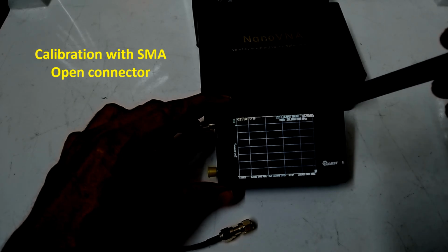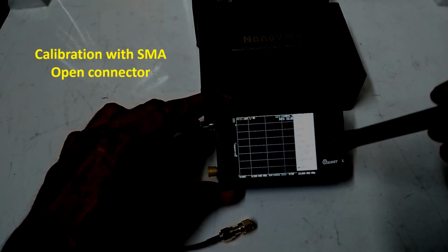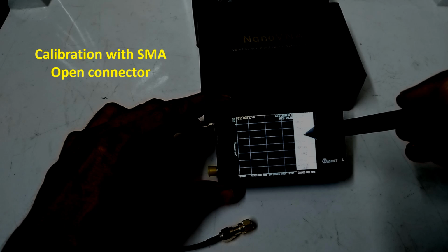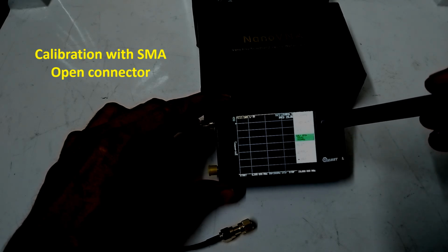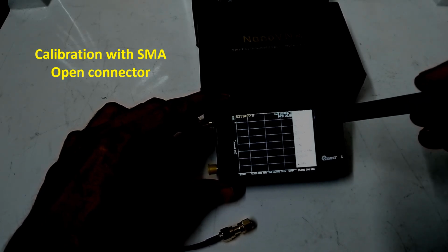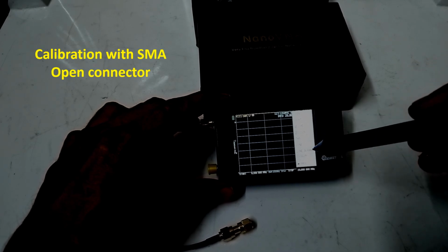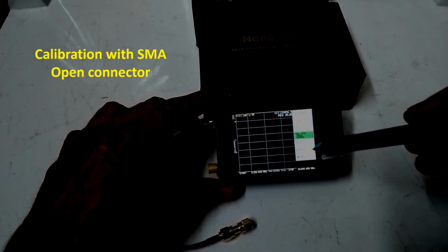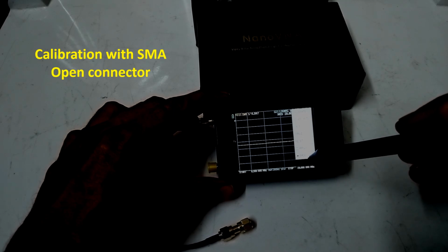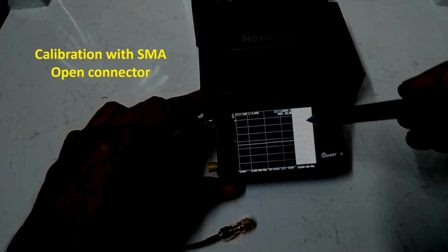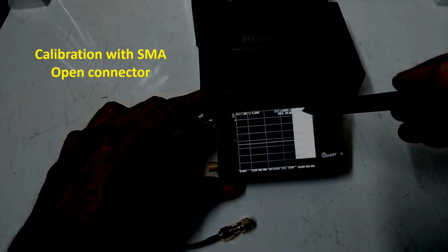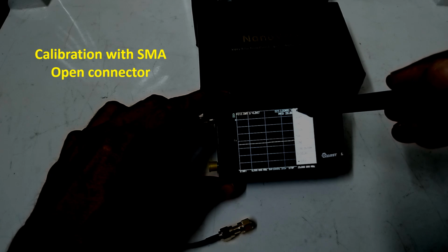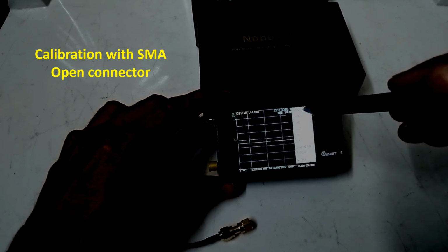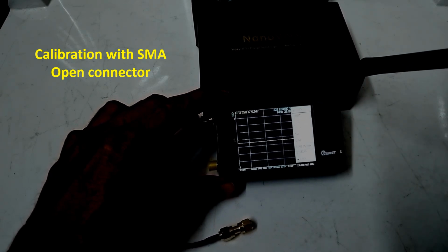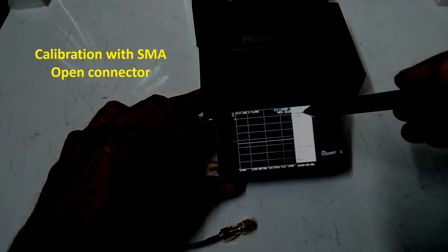Now we'll go for the calibration. Calibrate. First you have to reset the calibration. It has been reset. And calibrate. I am first calibrating open, SMA open. SMA open has been calibrated and it has moved to SMA short.